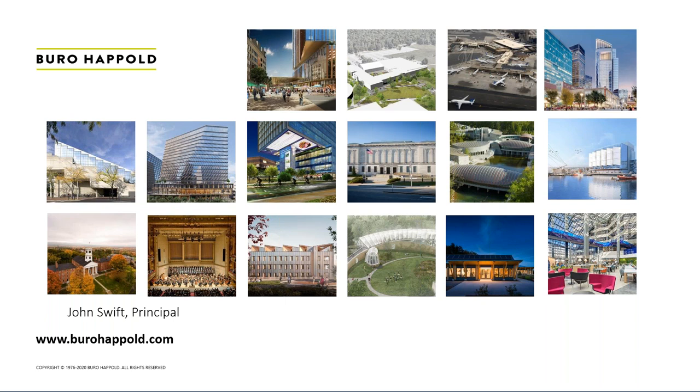Yeah, and somebody asked a COVID question earlier. One of the things that we're doing on all projects now is air quality monitoring, which obviously is a CO2 sensor, but other sensors too. You really want to make sure that you're delivering the minimum ventilation to the space. That's key. You're using the CO2 control level, and limiting inside there could drop you below the minimum ventilation rate. Yeah, but I'm talking about it the other way. Yeah, I'm saying you can only go so low. And if it allows you to go lower, don't allow it. Yep.